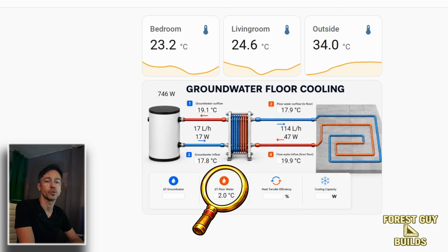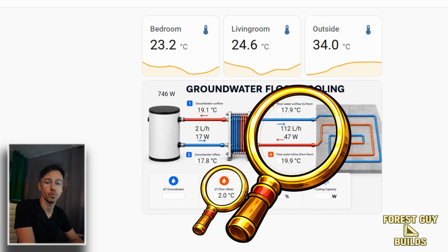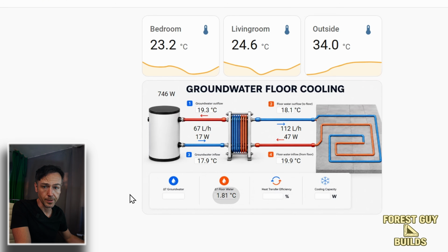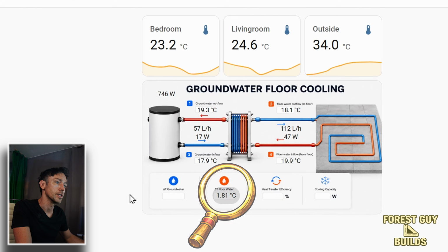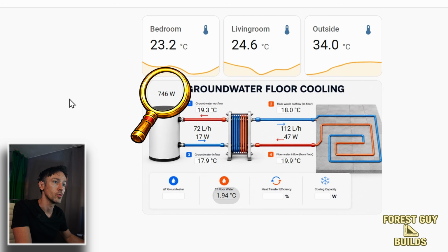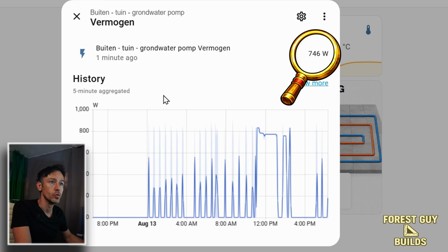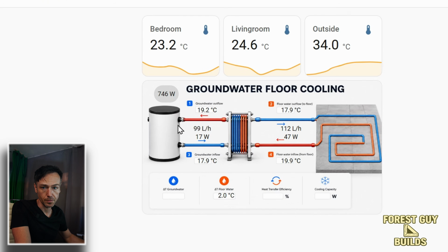I think one of the most important metrics here is the temperature difference between the supply and return temperature. This is actually fun to see, because we now see a quite small delta in the temperature of less than 2 degrees. This is because the buffer is almost empty, so at this moment it is refilling. We also see that at the power use of the groundwater pump - it is filling up, and the delta is increasing as well, because the reservoir is filled with fresh cooling water. We will see that it will increase over time during the video.